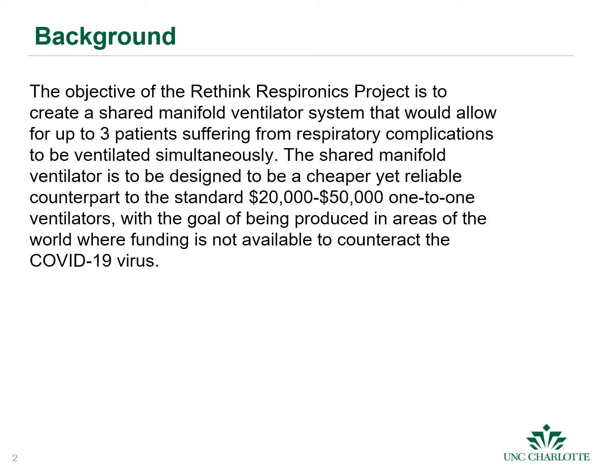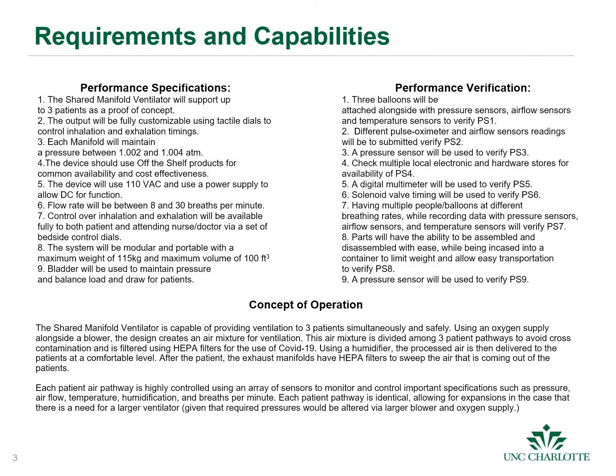available to hospitals. The most important specification listed here is that the shared manifold ventilator will support 3 patients, and to verify this, 3 test balloons will be attached to the ventilator alongside with several sensors. Looking at the concept of operation, the shared manifold ventilator can provide ventilation to 3 patients simultaneously and safely with the use of solenoid valves to control the mixture and flow of the air and oxygen. Each patient air pathway is identical and highly controlled by using several sensors.